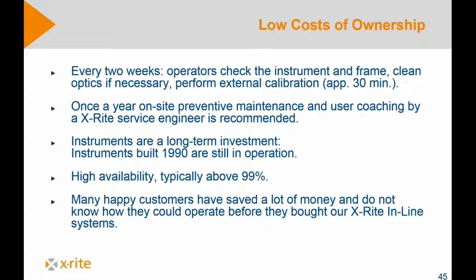Once a year, we recommend to have an on-site preventive maintenance from one of our service technicians. So somebody's coming over, cleaning the instrument from inside, doing calibrations, checking that everything works fine. We have capacitors inside which should be replaced every year. So this is done by the X-Rite service engineer. These instruments are a very long time investment. So we have instruments built in 1990, which are still in operation. Unfortunately for me, honestly, but we try to make good instruments and they last very long.